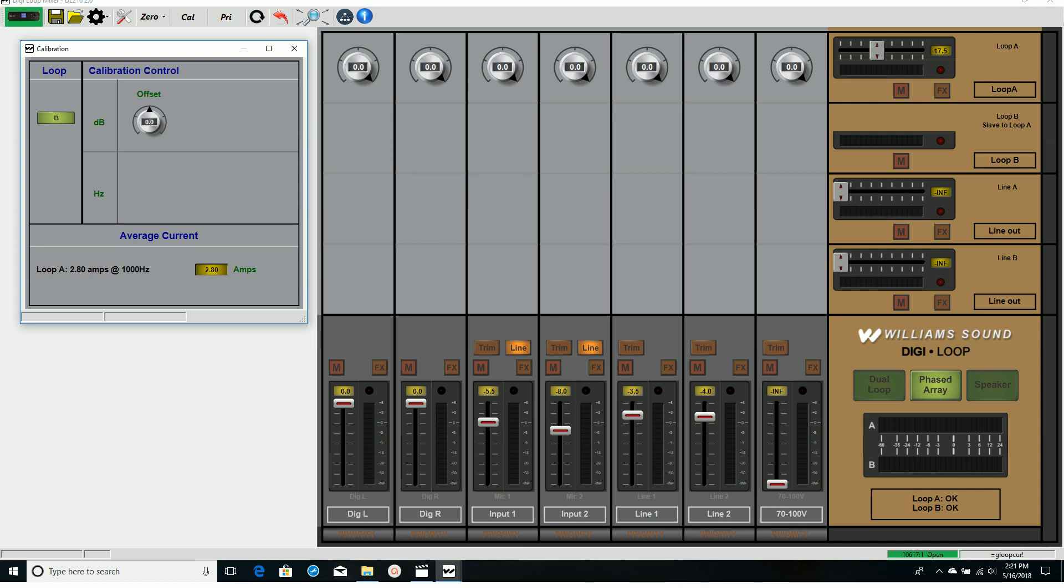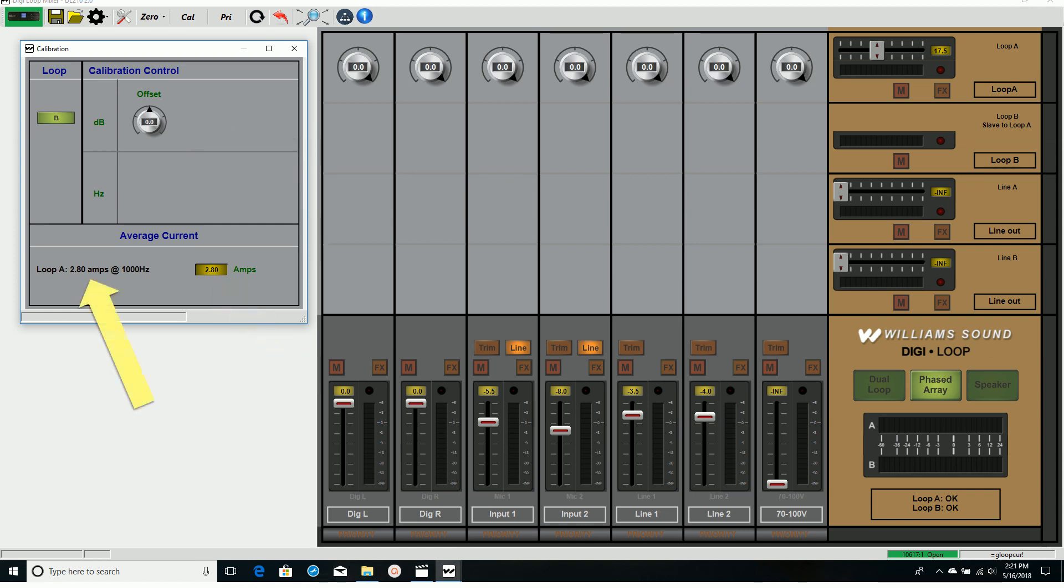Often the wire length in loop B will be shorter than loop A, so we have an offset to adjust loop B to deliver the same amount of current as we have in loop A.